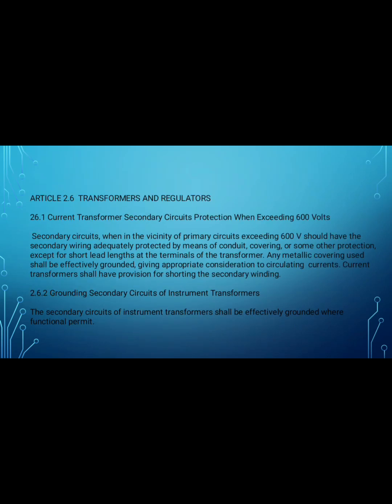Article 2.6 Transformers and regulators. 2.6.1 Current transformer secondary circuit protection when exceeding 600 volts. Secondary circuits in the vicinity of primary circuits exceeding 600 volts should have the secondary wiring completely protected by means of conduit, covering or some other protection, except for short leads at the terminals of the transformer. Any metallic covering used shall be effectively grounded, giving appropriate consideration to circulating current. Current transformers shall have provision for shorting the secondary winding.